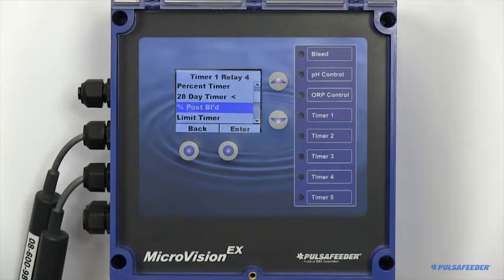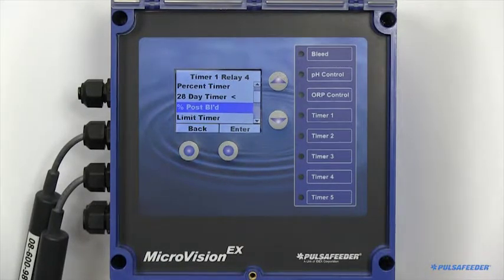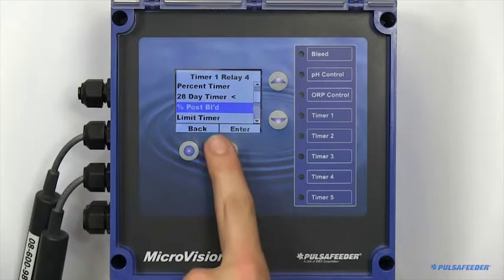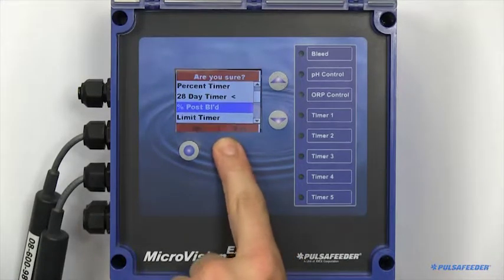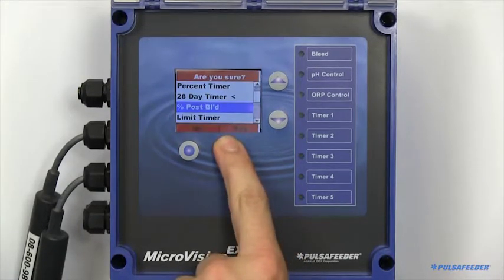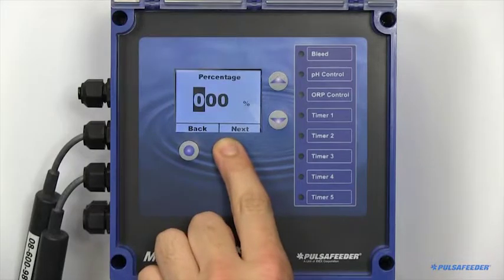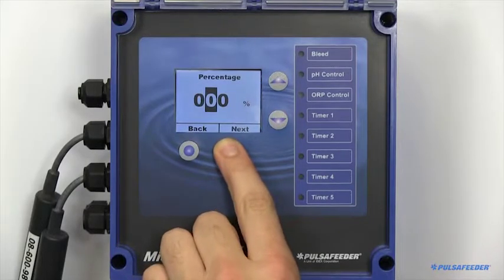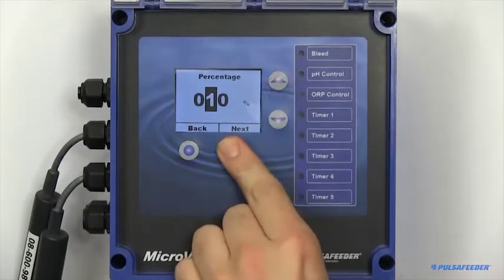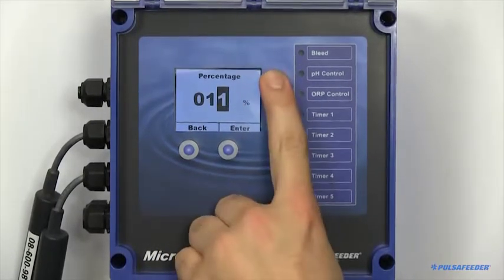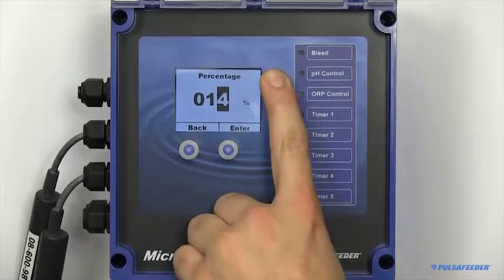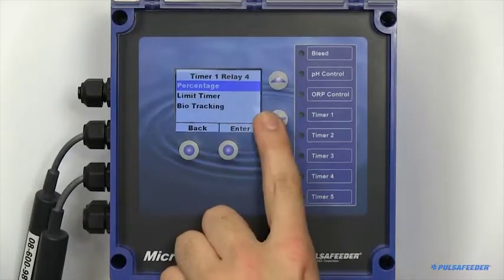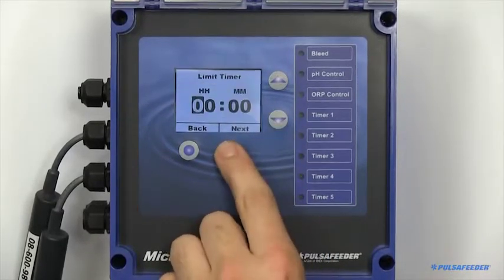Percent Postbleed keeps track of the time the bleed relay is turned on. When that bleed shuts off, it will then bleed for the specified percentage. The timer also includes a limit timer to prevent overfeeding.